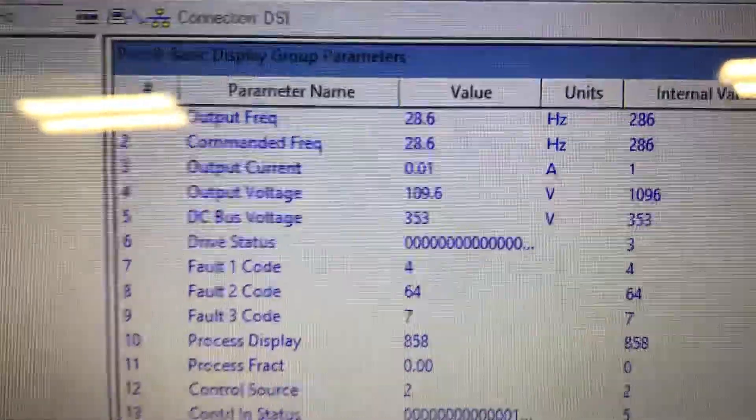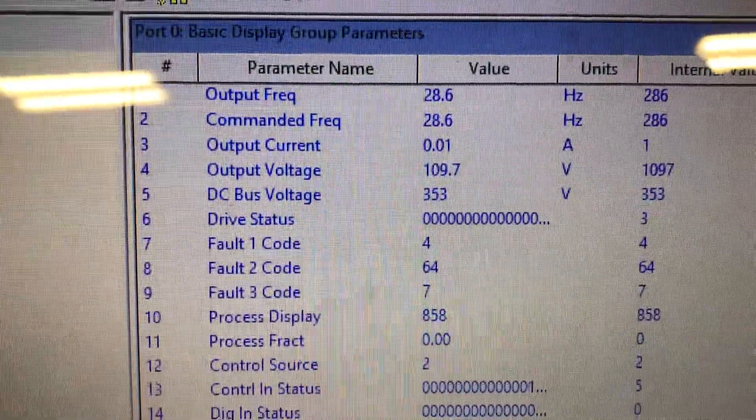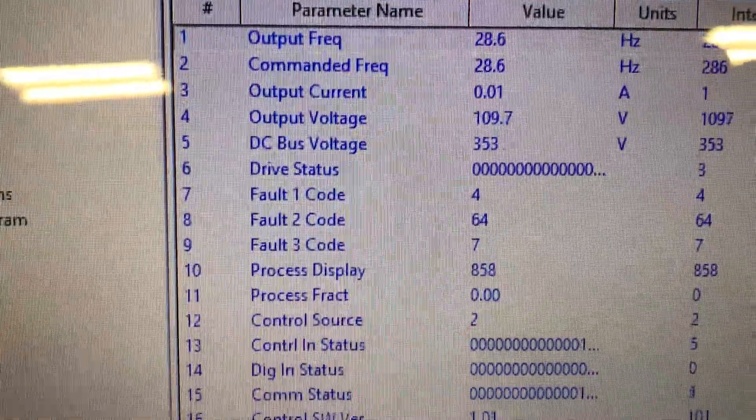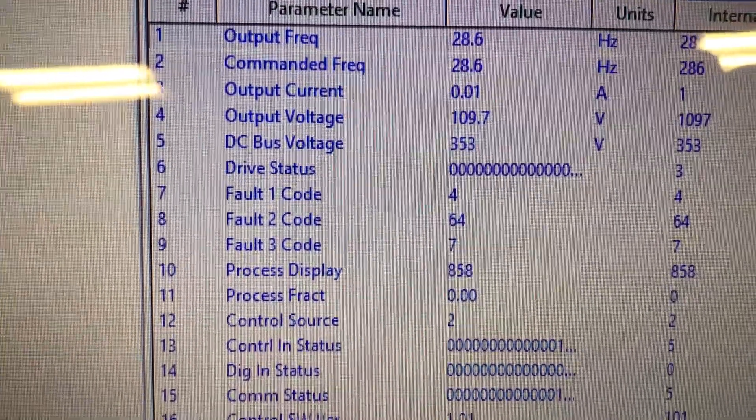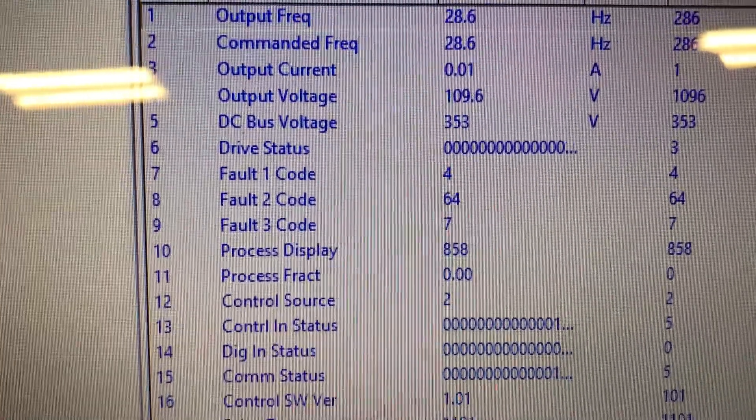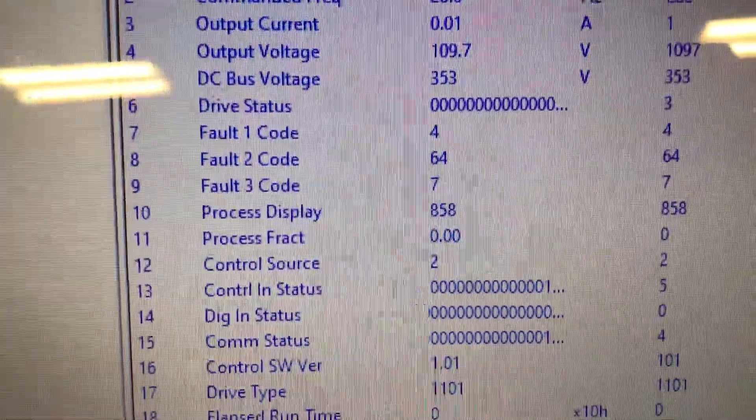Our software now tells us that the output frequency is 28.6 as commanded. Notice there's some current. The output voltage is now 109, and the DC bus is 353 volts, but I'm only putting in 120. So we can do magic with the inputs by using our electronics.